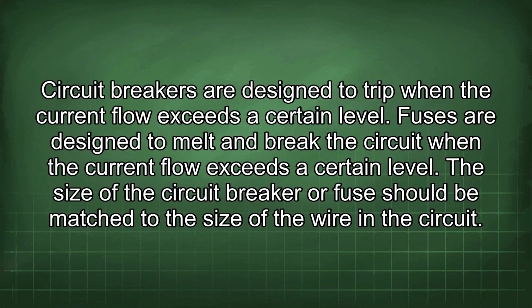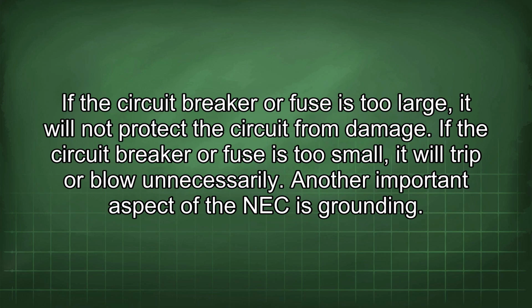The size of the circuit breaker or fuse should be matched to the size of the wire in the circuit. If the circuit breaker or fuse is too large, it will not protect the circuit from damage. If the circuit breaker or fuse is too small, it will trip or blow unnecessarily.